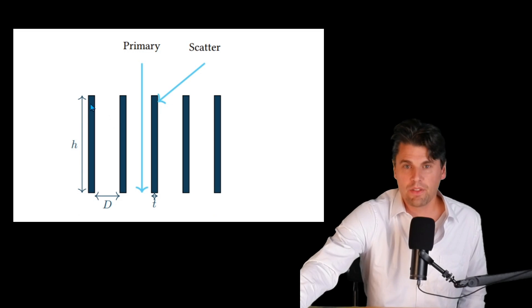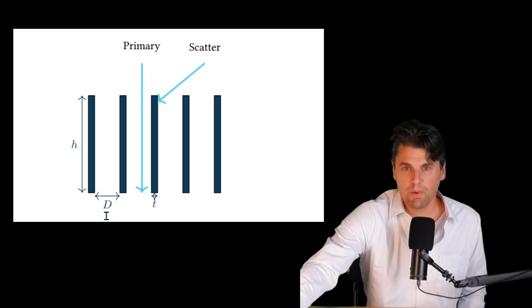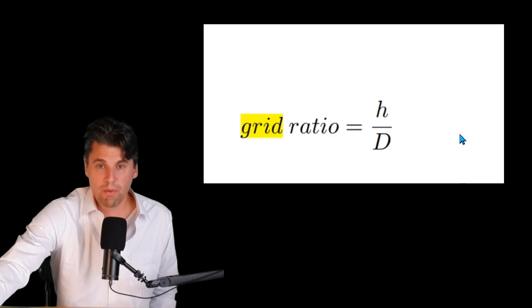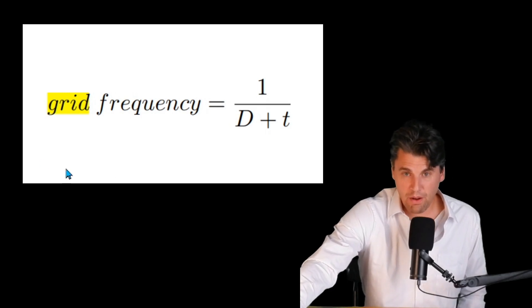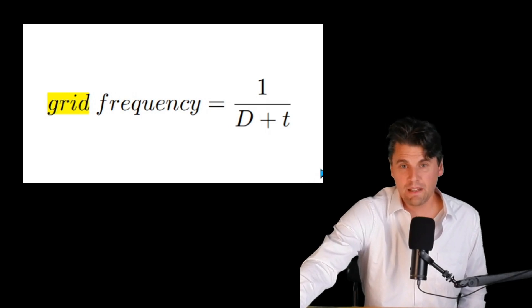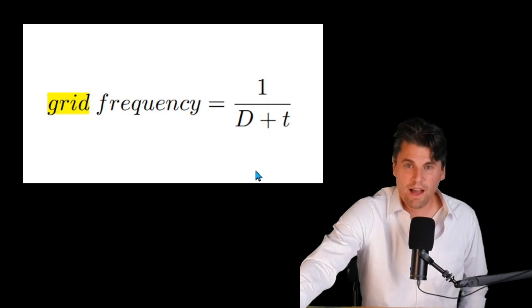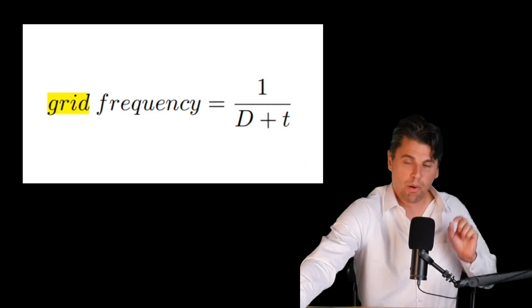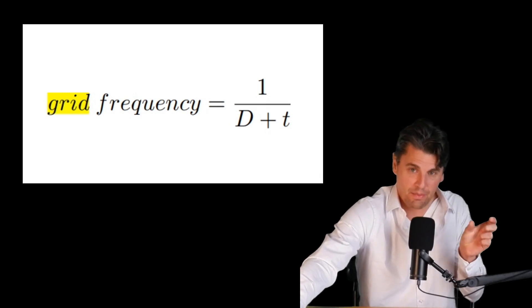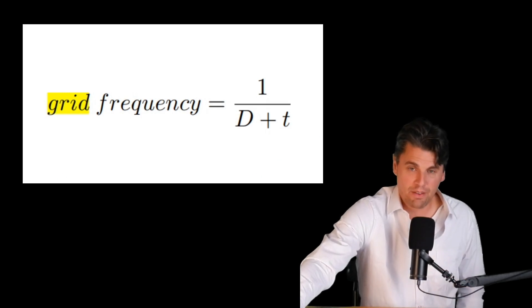We call these septa. H is the height of the septa, D is the distance between the septa, and t is the septa thickness. The grid ratio is the ratio of the height divided by the distance between the septa. The grid frequency describes how often the grid repeats itself — one divided by (d + t) — accounting for both the gap between septa and the septa size themselves.